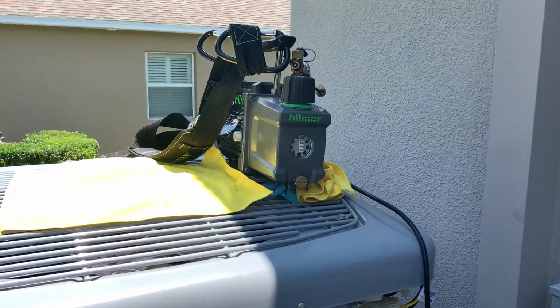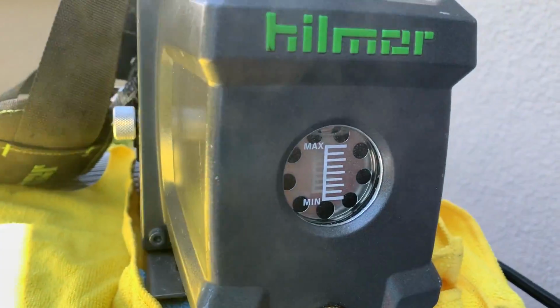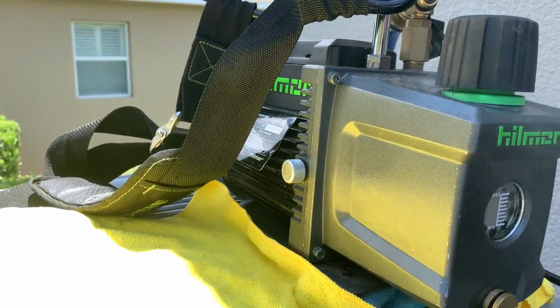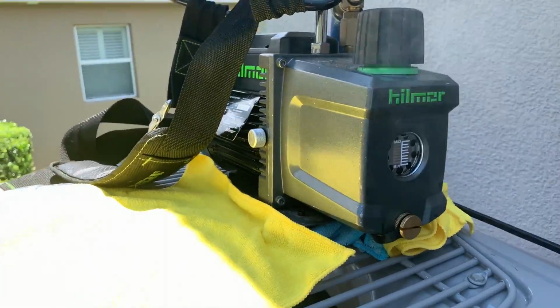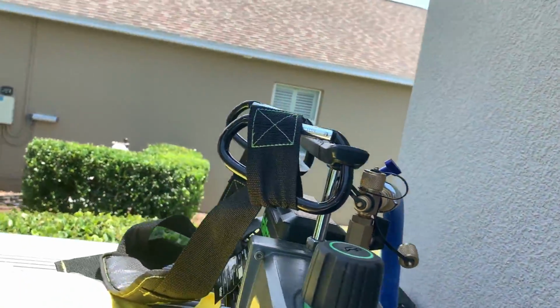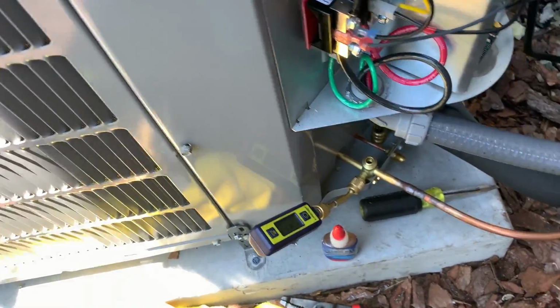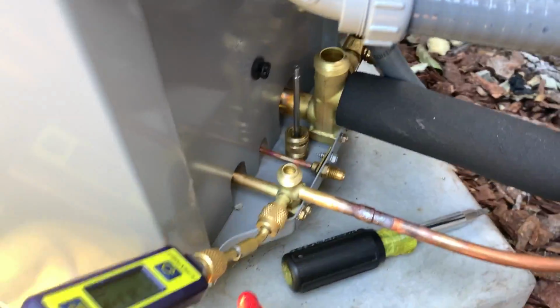All right, just kicked on the vacuum. Oil is clear, level is good. He's starting, Manny is a purist, so he's starting with the gas ballast open, and we're doing it the true blue way, the way we do every vacuum. True bluing it. Pulling from the suction side, and so that way it's got to pull all the way around.